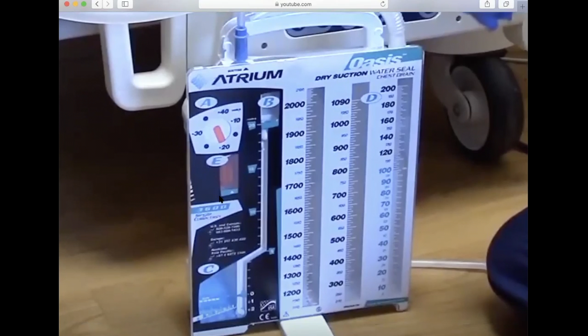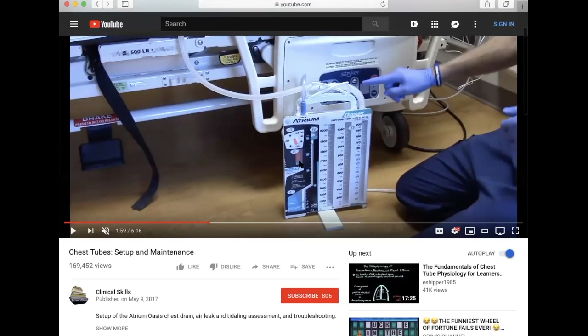The third chamber is called the suction control chamber. It provides suction control of the chest tube system. There are actually two forms of suction control. One is wet and one is dry. Let's start off with the dry system because that's what this appears to be. With dry suction, you can see there's no water added to the chamber. With no water, there's also no bubbling, right? What's in it looks like an orange floater ball that appears in this chamber and indicates proper suctioning.